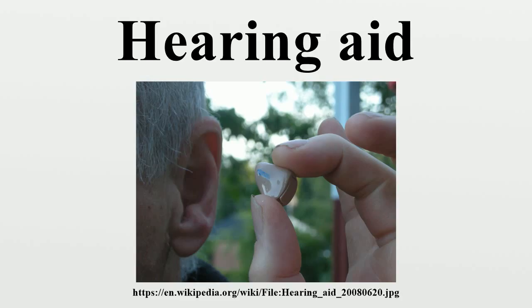Hearing aid outcome can be represented by three dimensions: hearing aid usage, aided speech recognition, benefit, satisfaction. The most reliable method for assessing the correct adjustment of a hearing aid is through real ear measurement.